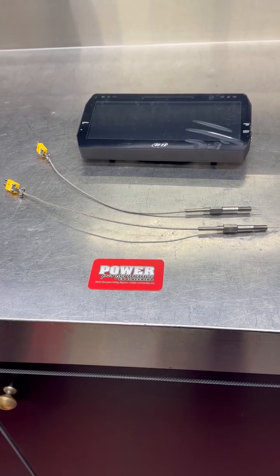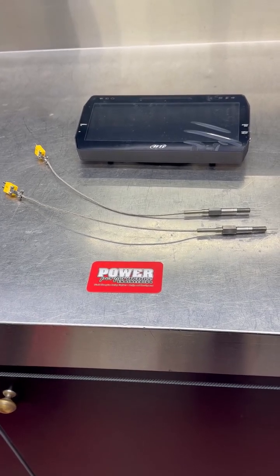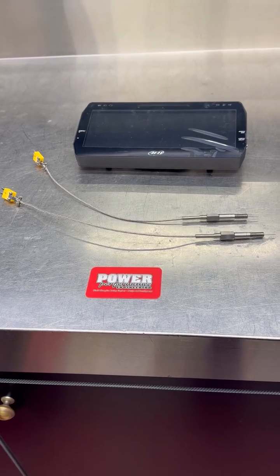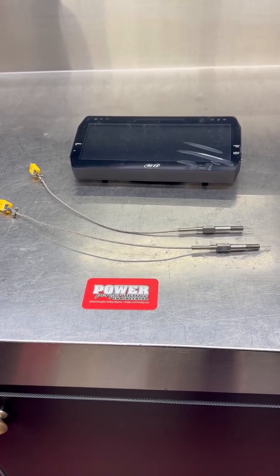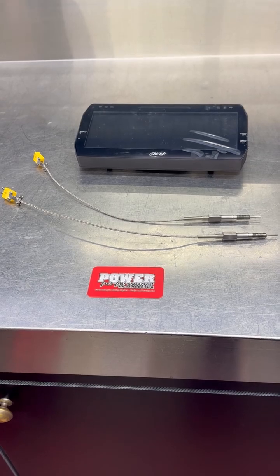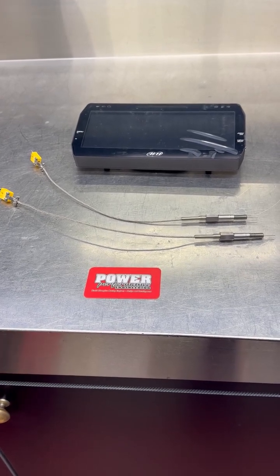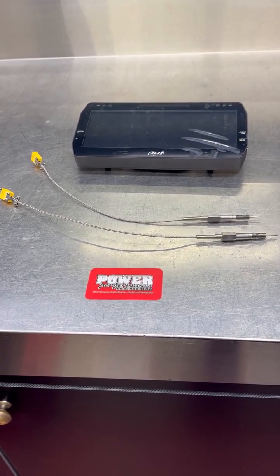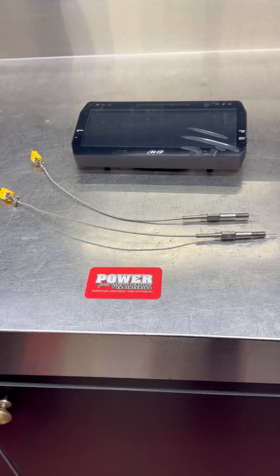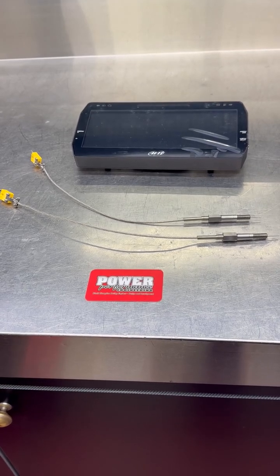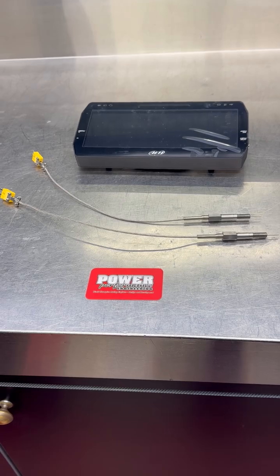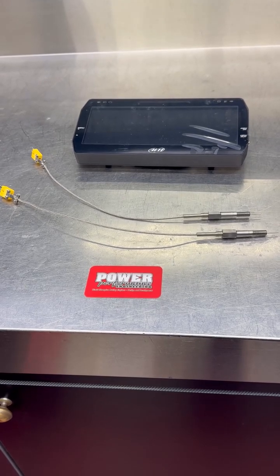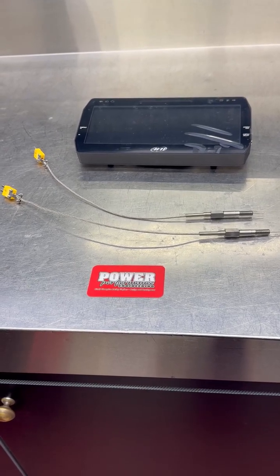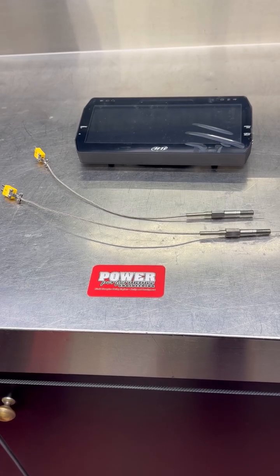One thing you want to be aware of is if you run extension cables, the wires are different in all K-type thermocouples. There is chromel, which is one of the wires, and the other one is alumel. Both of those wires carry different properties and different resistances. This is actually how this works. So be aware you can't just run two wires to the front to whatever dash you're using. It is not going to work correctly.